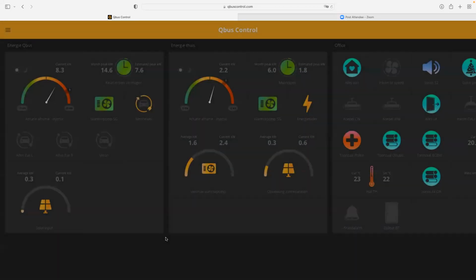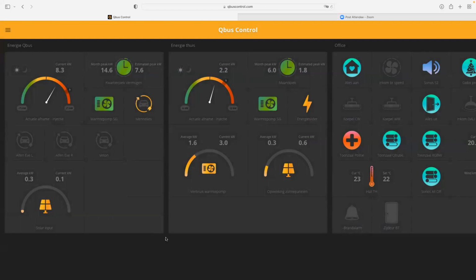Why do you want to set this maximum? Because we have 30 kilowatts of solar on the roof. If the solar is generating 10 kilowatts, we want to purchase a maximum amount as well, let me check where we've set that level. We want to purchase a maximum of, let's say, 7.5 kilowatts, though we can go up to 17.5.